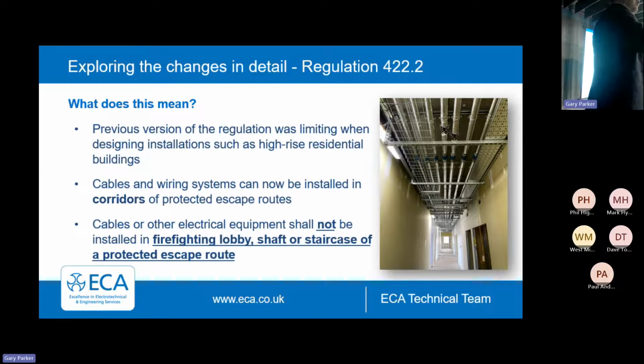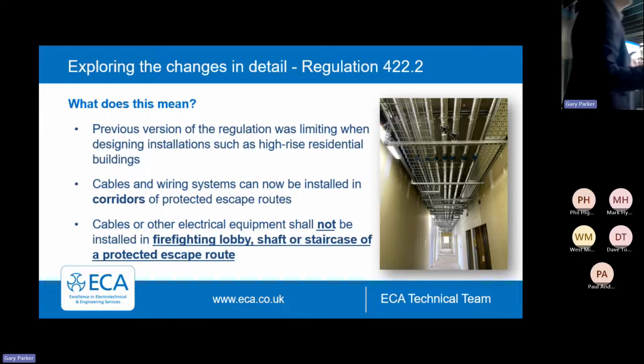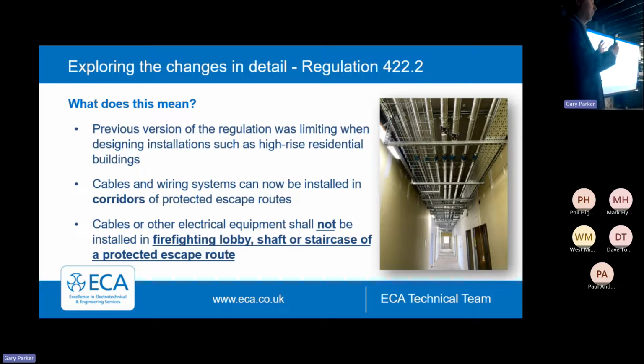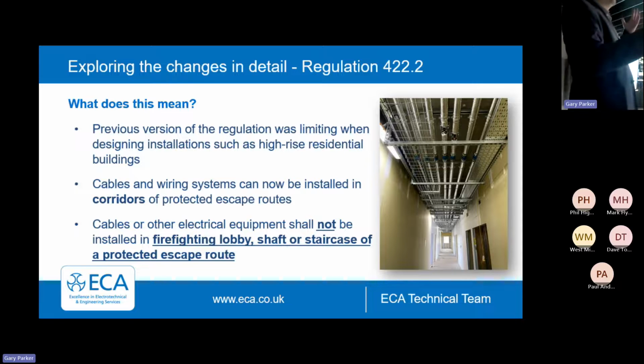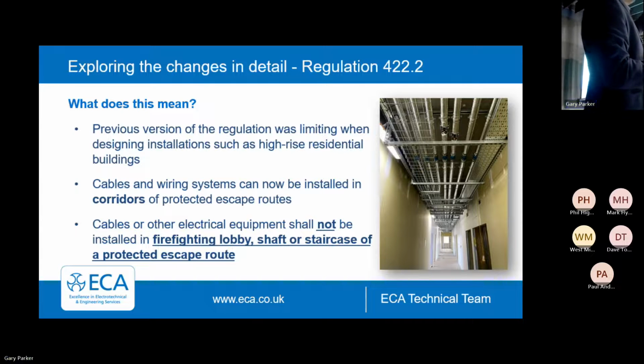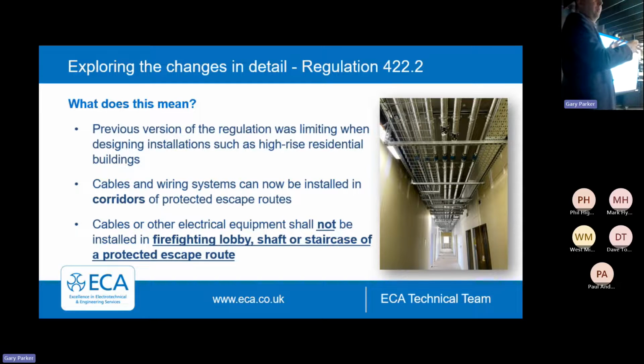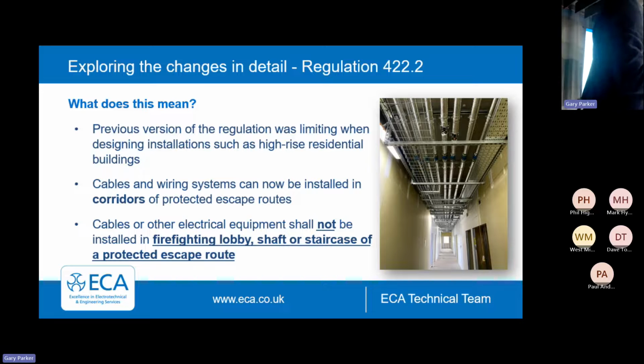So in your house, you won't necessarily have metal clips. You're not prohibited from doing it, but the fire rating of that 30-minute fireboard or plasterboard is going to give you sufficient time, hopefully, to get out. We're not designing the electrical installation to hold up the building - we're designing it to be, the phrase is, protected against premature collapse to allow firefighters access and egress.